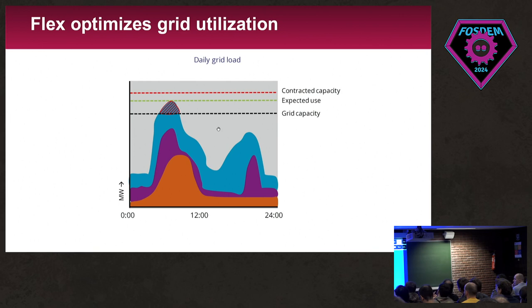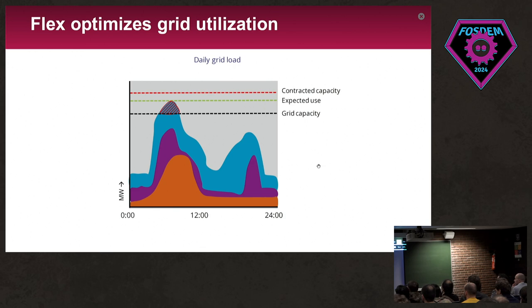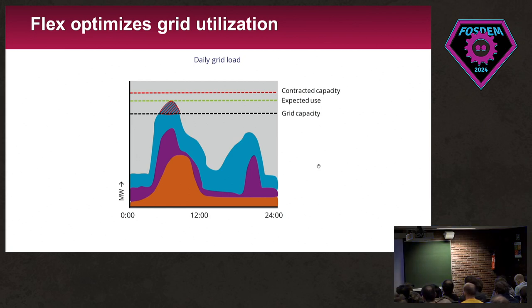We can fix this problem by making sure consumption doesn't go over the peak anymore. There are some major users on the net — let's say above one megawatt for their connection — that have some influence on when their energy is used. For example, a giant freezer or a stored battery: the temperature needs to be between minus 25 and minus 20, so if you don't use power at the peak, you can make sure the problem is fixed.